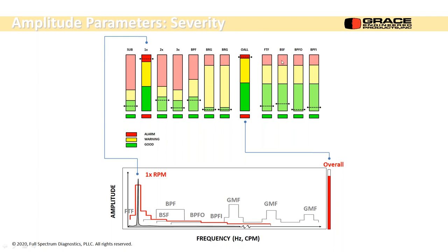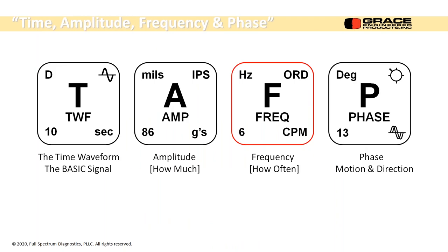If I know the bearings themselves, what make and model number it is, I can put a very narrow band in there and look for these frequencies to appear. And it's very subtle stuff in the background noise. It would be very interesting to pull those out statistically, which shouldn't be too bad. We're going to look at the frequency now, how often something happens.